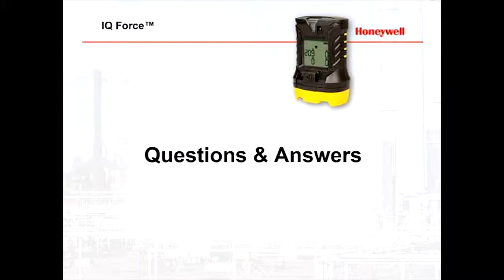I got a question here from Glenn. Can the docks be gang banked? For example, can 6 docks, 1 cylinder, and 1 regulator? Yes. So we'll support up to 5 docks. So I think the question said 6. We'll support up to 5 docks. They don't natively gang, but what we sell is an extra kit that's basically just some tubes and some fittings. And then in behind the scenes, what you do is you connect a demand flow regulator, and then you would have 5 docks running off the same header of tubing into the one demand flow regulator.